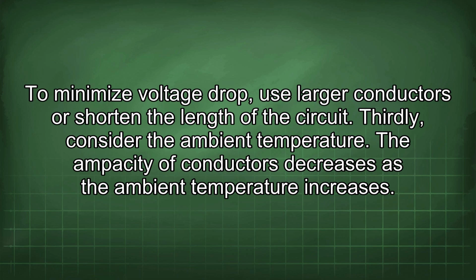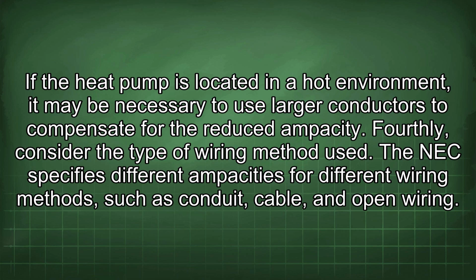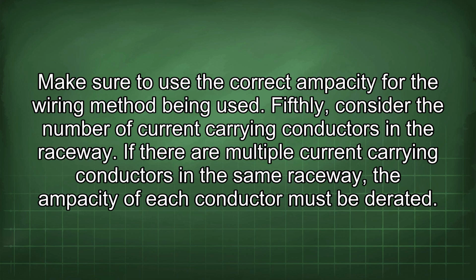Thirdly, consider the ambient temperature. The ampacity of conductors decreases as the ambient temperature increases. If the heat pump is located in a hot environment, it may be necessary to use larger conductors to compensate for the reduced ampacity. Fourthly, consider the type of wiring method used. The NEC specifies different ampacities for different wiring methods, such as conduit, cable, and open wiring. Make sure to use the correct ampacity for the wiring method being used.